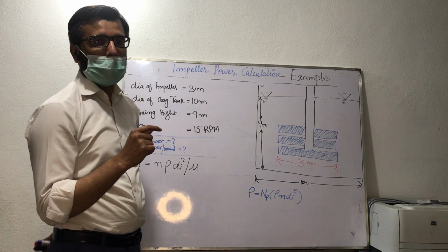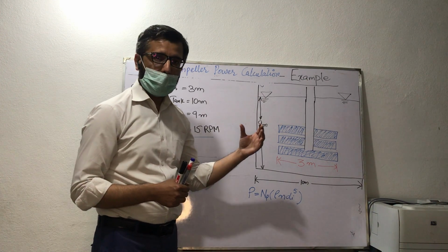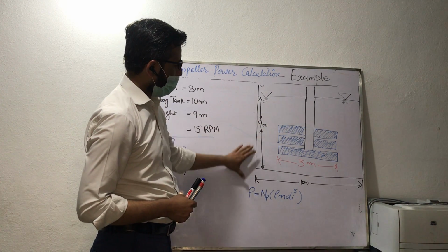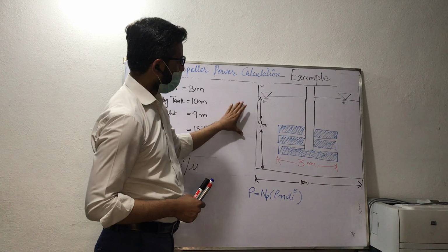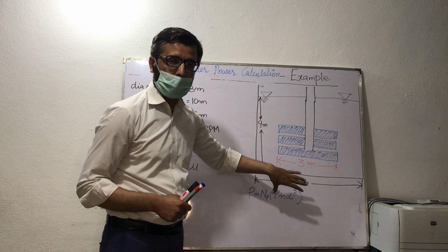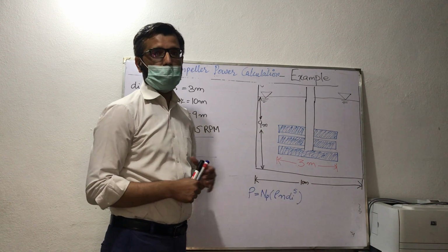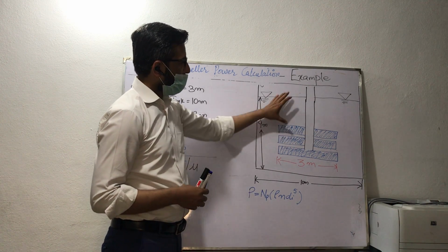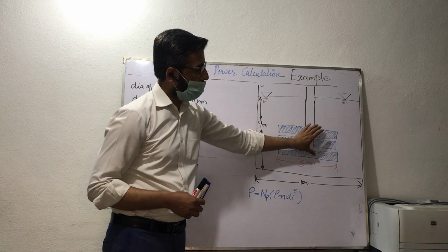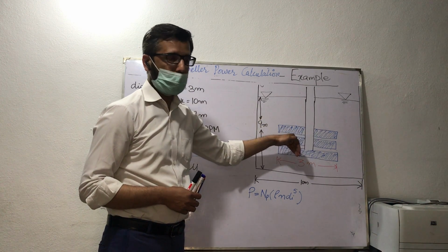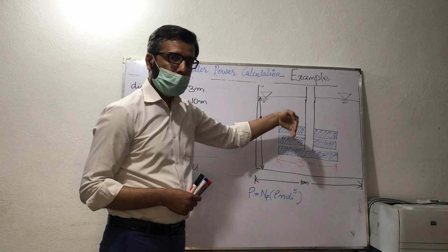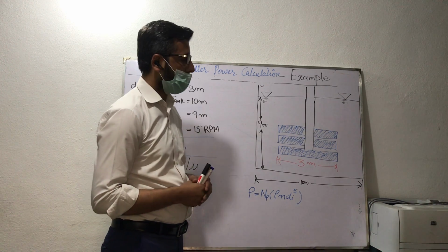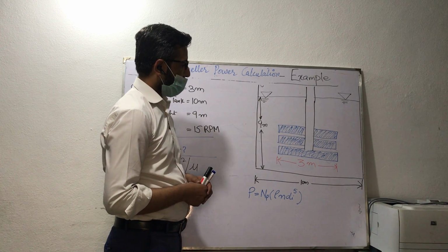If I would like to elaborate the dimensions of this coagulation chamber, we have this coagulation chamber which is almost 10 meters, having 10 meters of width. So its diameter is 10 meters, and we have installed a 6-blade impeller inside the coagulation chamber for rapid mixing of coagulant or the alum, or whichever chemical is being used for the coagulation.